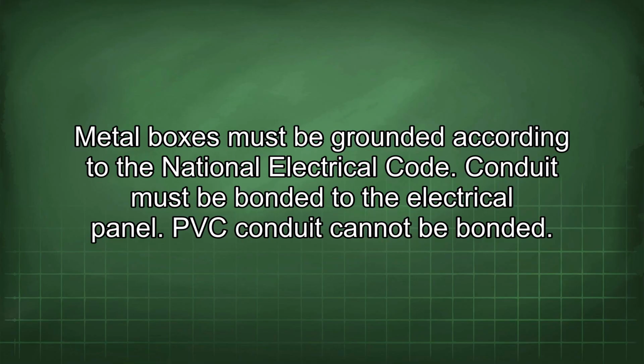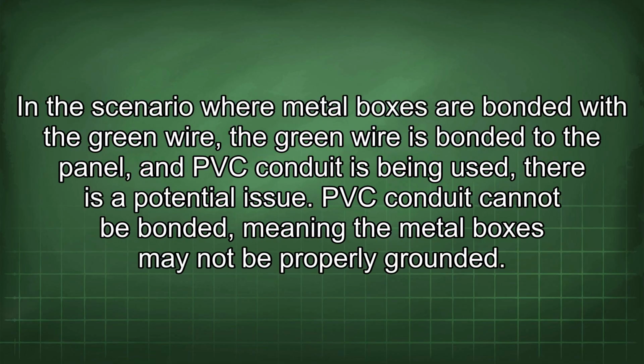Metal boxes must be grounded according to the National Electrical Code. Conduit must be bonded to the electrical panel. PVC conduit cannot be bonded. In the scenario where metal boxes are bonded with the green wire bonded to the panel and PVC conduit is being used, there is a potential issue. PVC conduit cannot be bonded, meaning the metal boxes may not be properly grounded.